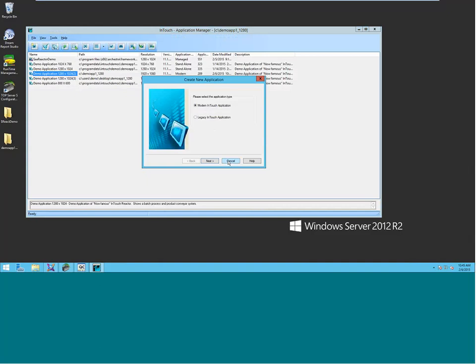And then does the alarms logged to history block count as one historized tag license? Oh, that's a good question. No, they do not. So just like the traditional alarm database, alarms that are logged, those are not counted as tags. So alarms that are saved to the historian and history blocks do not count against the historian tag count.